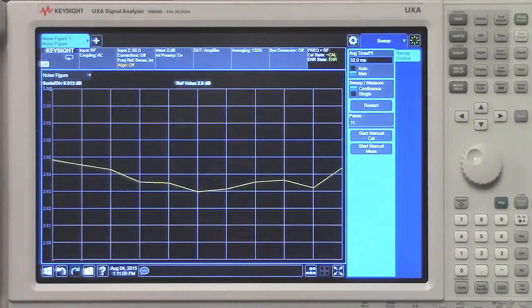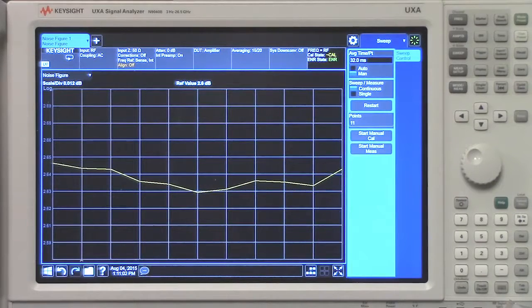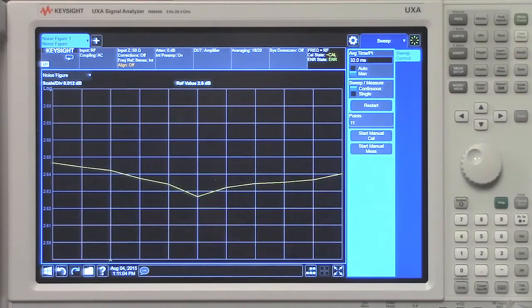If you can't afford longer measurements, then at least use averaging during calibration. This is not as effective as using averaging consistently, but it will improve your accuracy regardless.